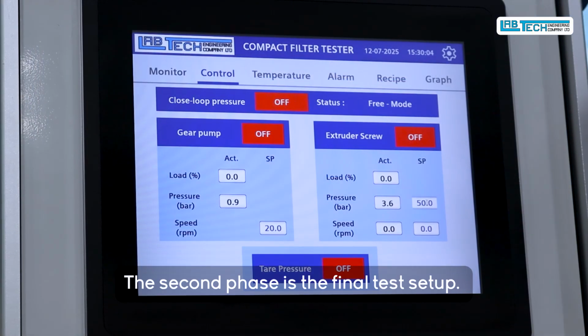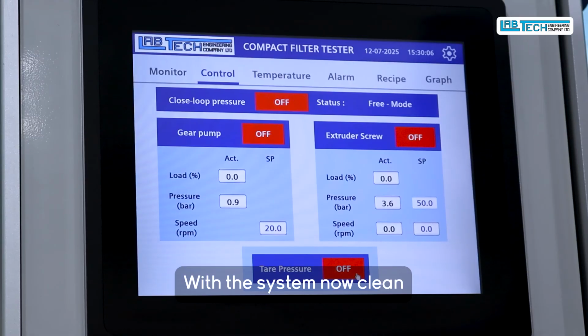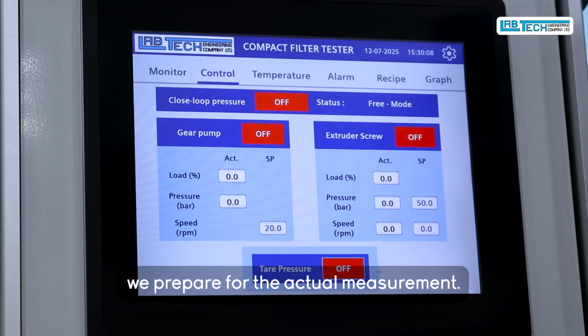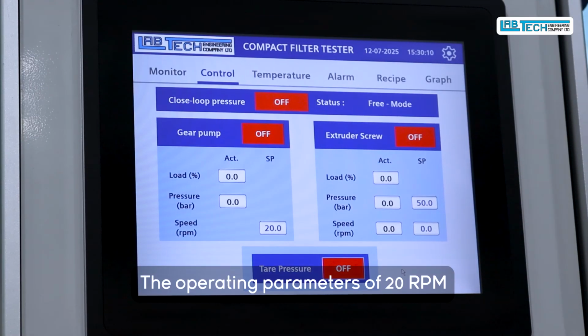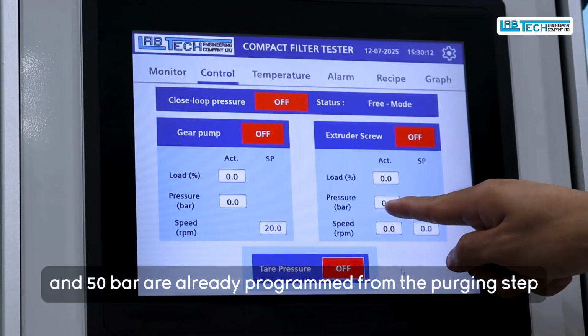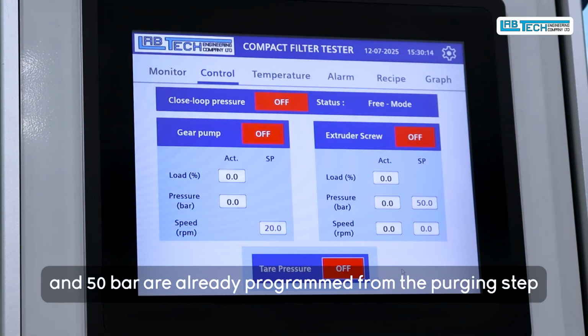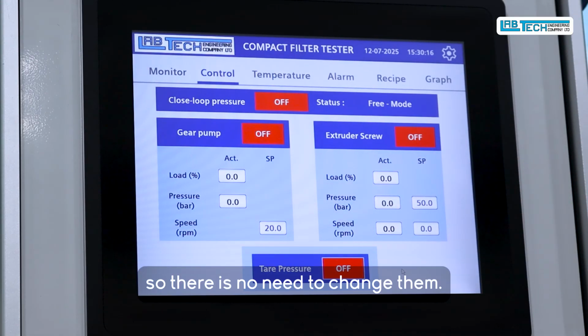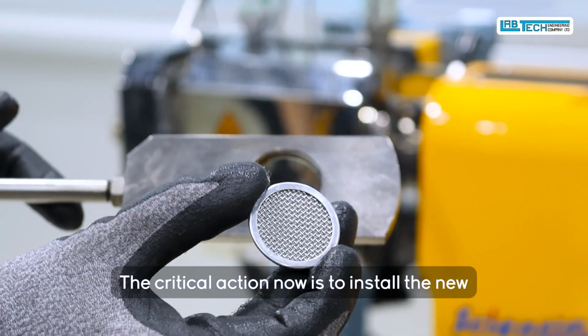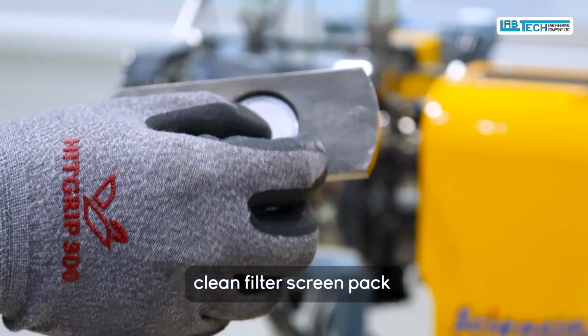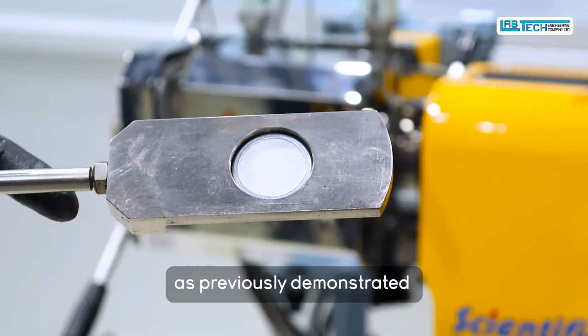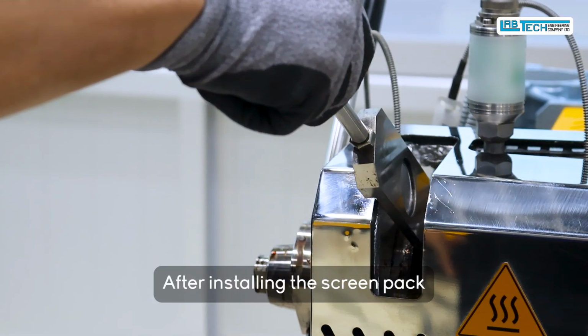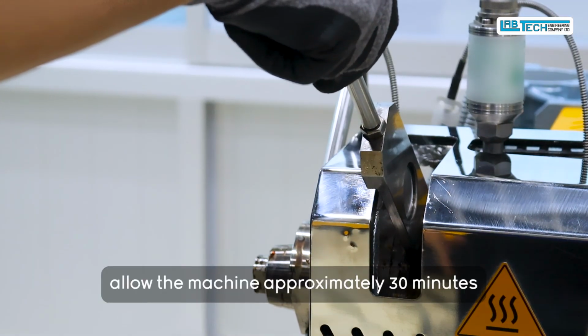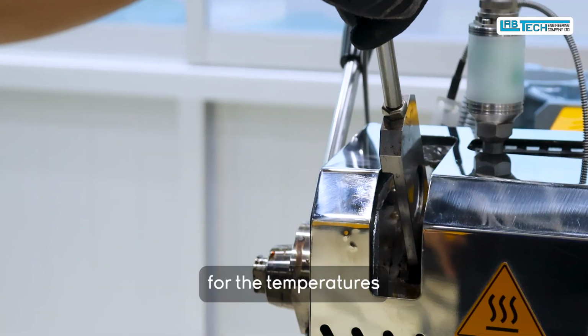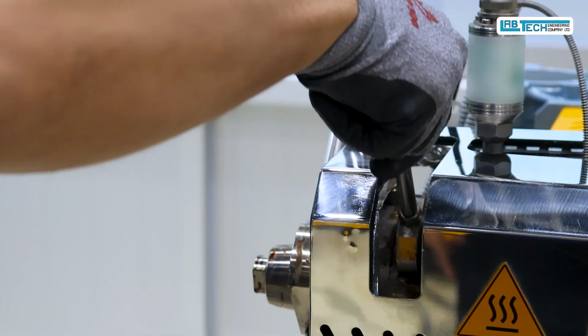The second phase is the final test setup. With the system now clean, we prepare for the actual measurement. The operating parameters of 20 RPM and 50 bar are already programmed from the purging step, so there is no need to change them. The critical action now is to install the new clean filter screen pack as previously demonstrated. After installing the screen pack, allow the machine approximately 30 minutes for the temperatures to fully stabilize throughout the head assembly.